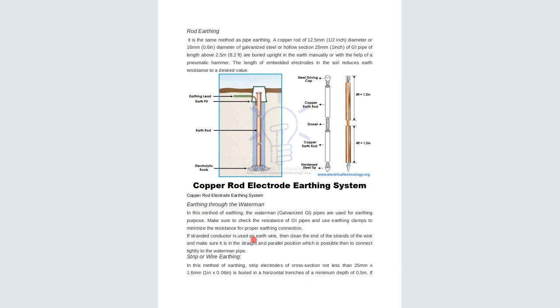The earthing through the water main is another form of earthing. In this method of earthing, a water main galvanized pipe is used for earthing purposes. So make sure that they check the resistance of the GI pipes and use earthing clamps to minimize the resistance for a proper earthing connection. If a stranded conductor is used on the earth wire, then clean the end of the strand of the wire and make sure it is in a straight and parallel position, if possible, and then connect it tightly to the water pipe.